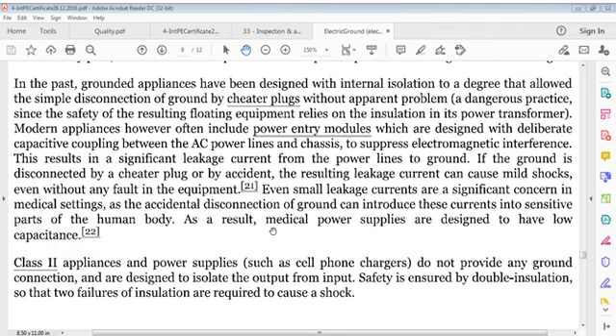In the past, grounded appliances had been designed with internal isolation to a degree that allowed simple disconnection of ground by cheater plugs without apparent problem. This is a dangerous practice, since the safety of the resulting floating equipment relies on an insulated power transformer.